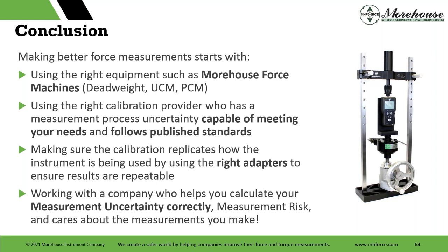So the other piece of that is a calibration provider who has measurement process capable of meeting your needs and follows published standards. That showed you a little bit about the standards there. Right adapters, and then measurement uncertainty. Look, if we don't calculate measurement uncertainty correctly, we do not have measurement traceability. And if we do not have measurement traceability, what is the overall value of that calibration?